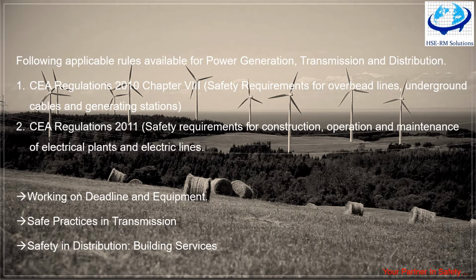Now let us understand some safe practices of transmission. So let us discuss the list of safety devices to be used on overhead transmission lines. The rules stipulate that every uninsulated line erected in a public place shall be provided with an approved device rendering the line safe if it should break. Guard wires must be provided above or below power lines when they cross telephone or telegraph lines.